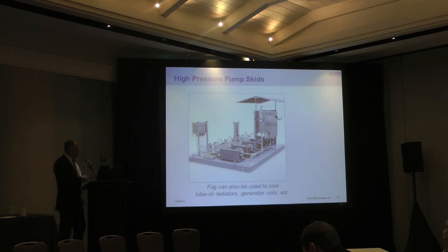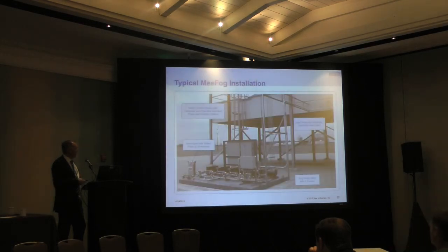And then one problem we notice with CAT pumps is when you have demineralized water, the high pressure seals wear out quickly because the demineralized water is a poor lubricant. It actually washes the lubricant out of the seals. So CAT pump developed a thing they call a seal flush system that allows you to operate 6,000 to 8,000 hours between changing of seals to reduce the maintenance requirement. And that's a typical installation.